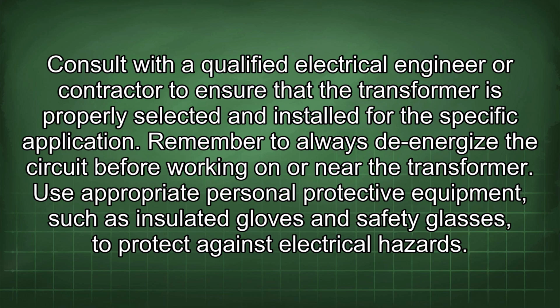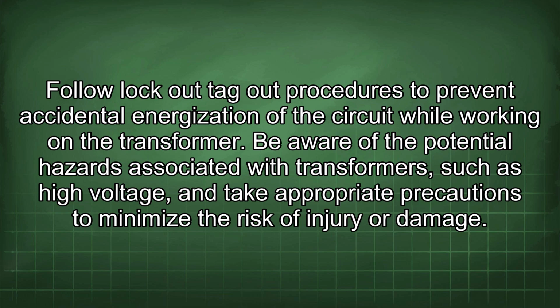Remember to always de-energize the circuit before working on or near the transformer. Use appropriate personal protective equipment, such as insulated gloves and safety glasses, to protect against electrical hazards. Follow lockout-tag-out procedures to prevent accidental energization of the circuit while working on the transformer. Be aware of the potential hazards associated with transformers, such as high voltage, and take appropriate precautions to minimize the risk of injury or damage.